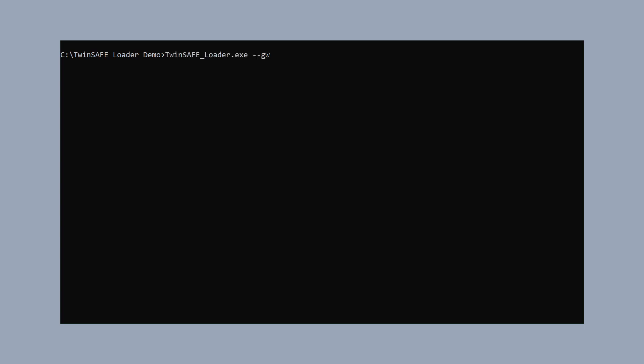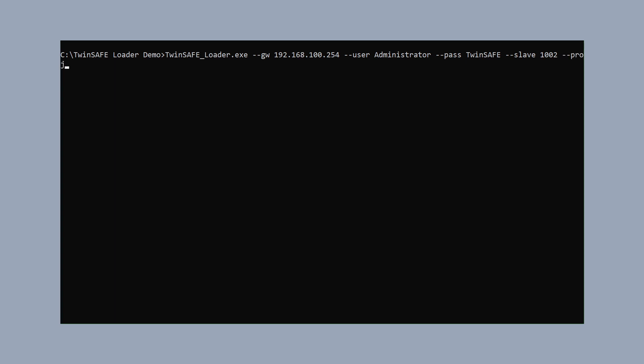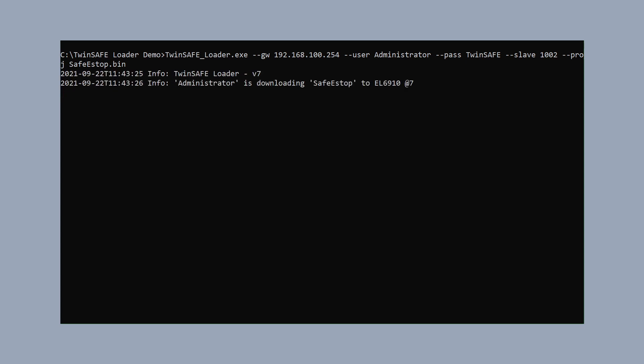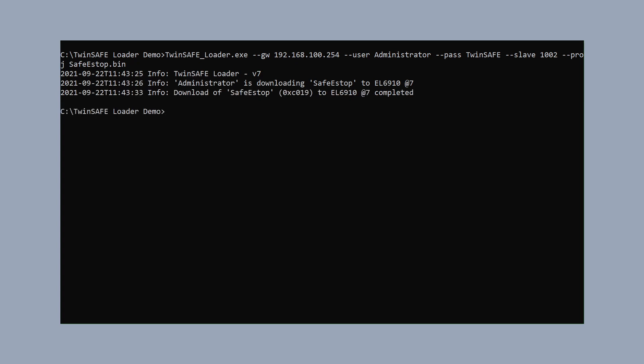For the download, we call the TwinSAFE Loader with our gateway configuration, entering the gateway IP address, the username and password for the EL6910 (which is the default), the slave address 1002 from the EtherCAT configuration, and with the parameter 'project' we hand over the binary file. After acknowledging the command, the TwinSAFE Loader downloads the safety project to the EL6910.